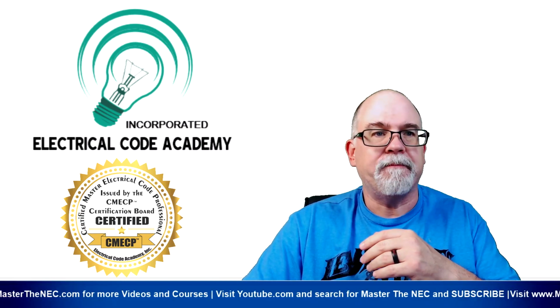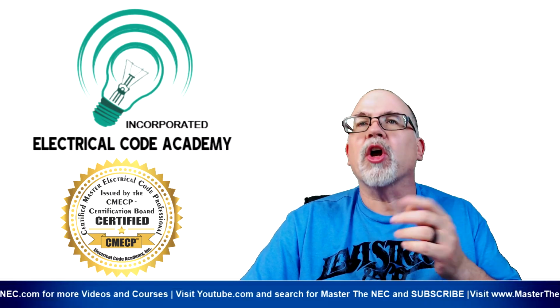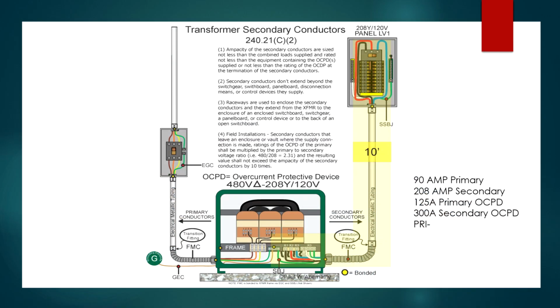It shouldn't be complicated. Now we're going to move on into this one: transformer secondary conductors, dealing with 240.21(C)(2) for today. Now we have 4 different rules here that we have to follow in order to be able to utilize these conductors up to 10 feet without overcurrent protection right here where they get their source, which here is the X1 and all that right here. So we're going to deal with these conductors.